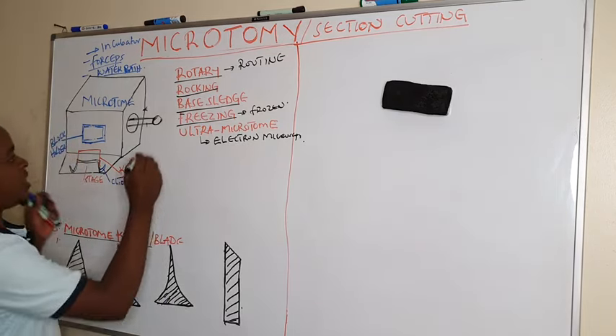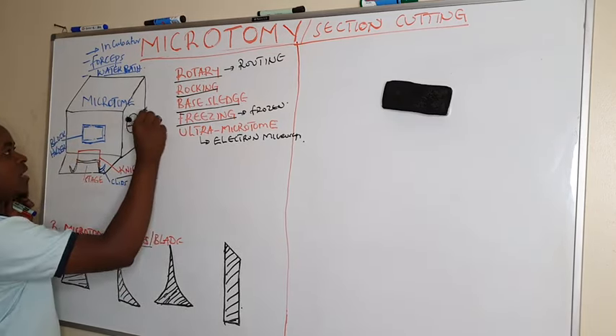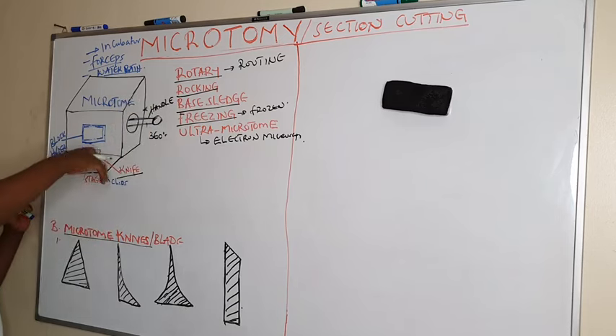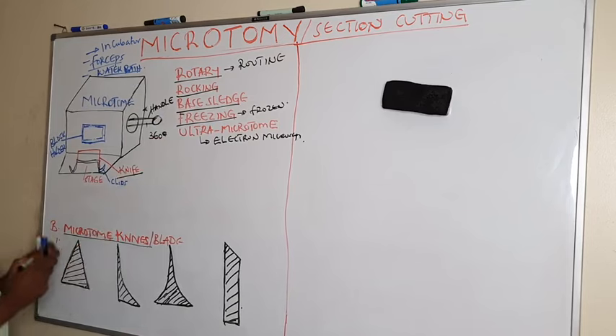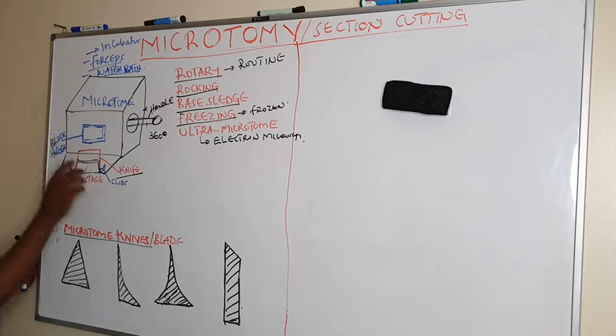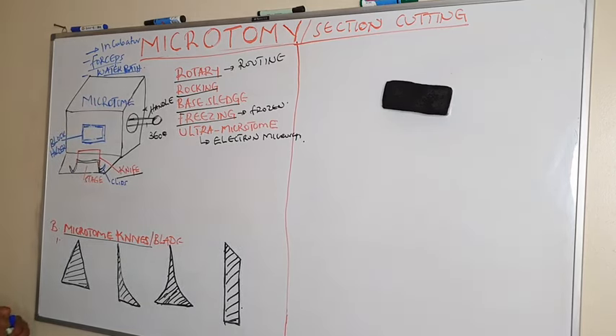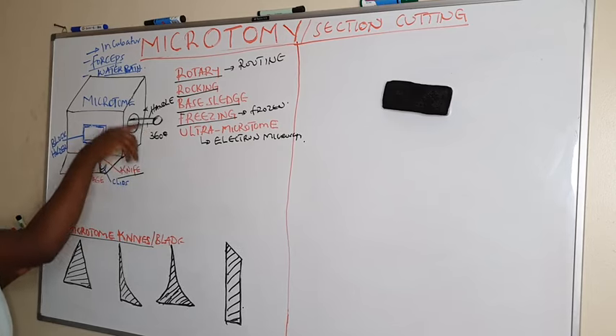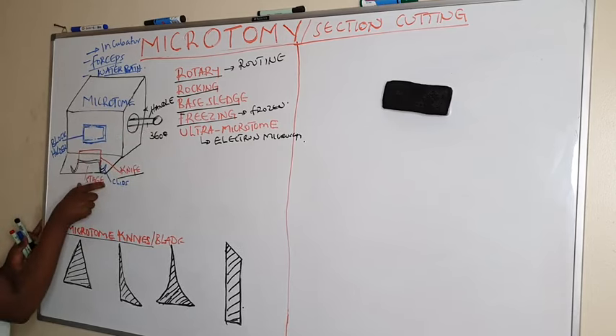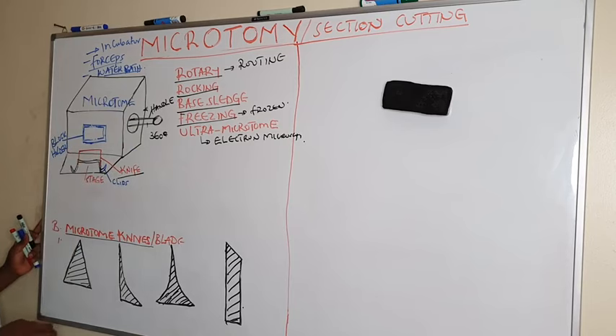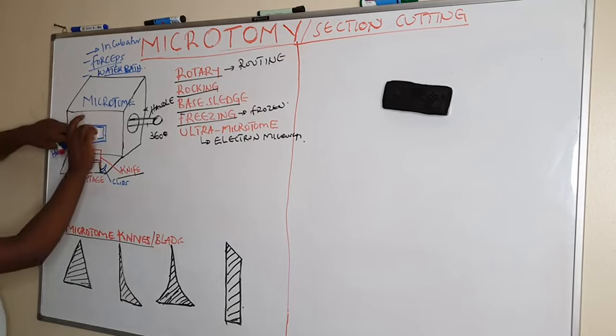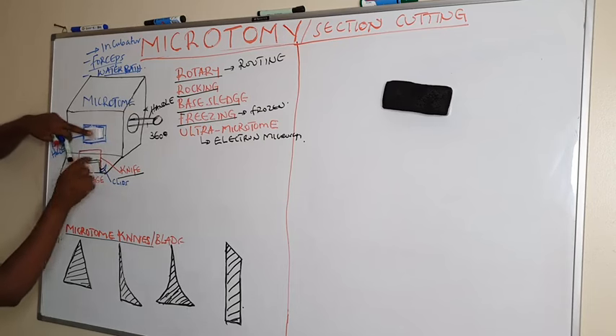The handle is moved by the right hand at an angle of 360 degrees, as the block on the block holder moves past the stationary knife. The structure of the Rotary Microtome includes the handle, the body, the knife holder, and the block holder. The block which is embedded is always placed on the block holder, and when we move the handle, it makes the block move past the stationary knife.